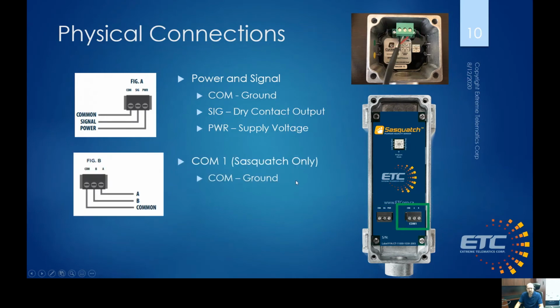Now, on the Sasquatch, there's an additional connector. This is for that Modbus RS485 slave connection. And so, once again, there's a COM in there, and then there's an A and B, which is a 2-wire RS485. With the Cyclops, the SIG pin is used for that 1-wire RS485 interface. So we do have a special circuit that's implemented in our link device connection that allows you to connect to the Cyclops without having to use a regular RS485.